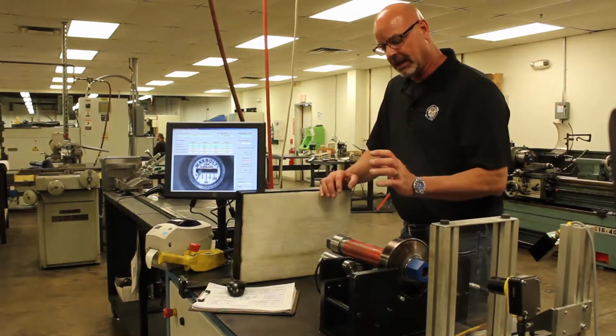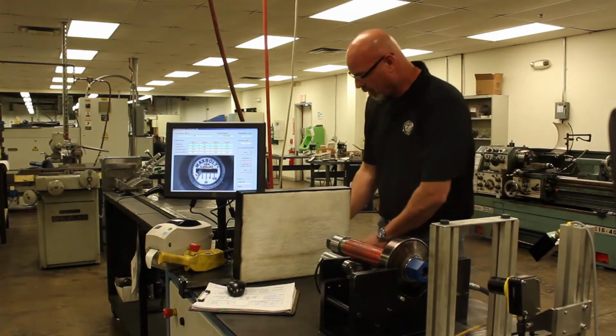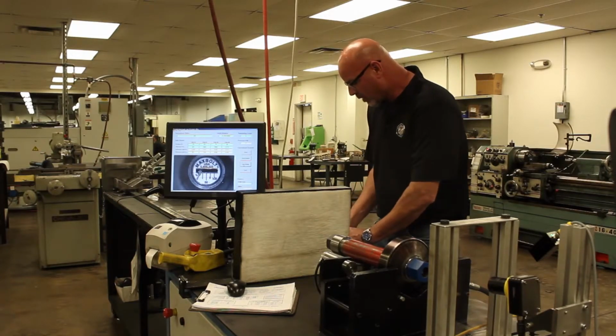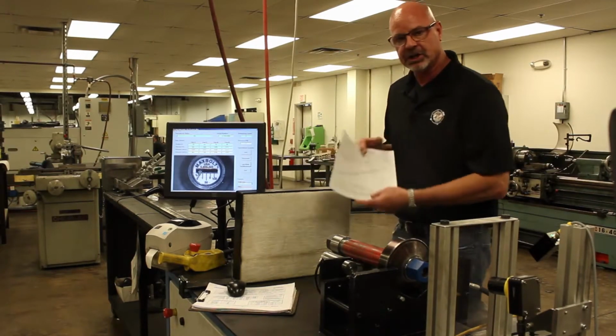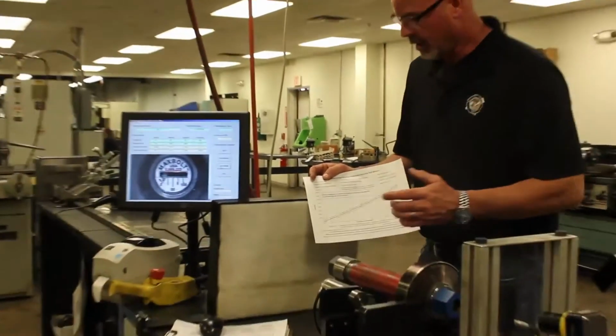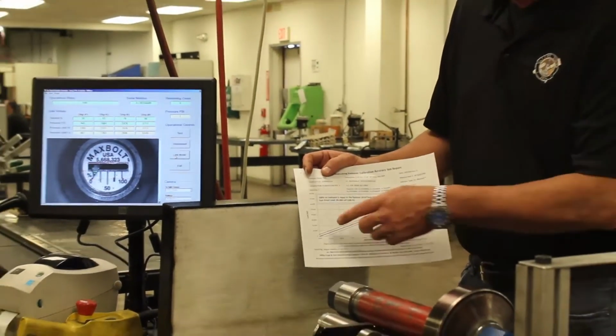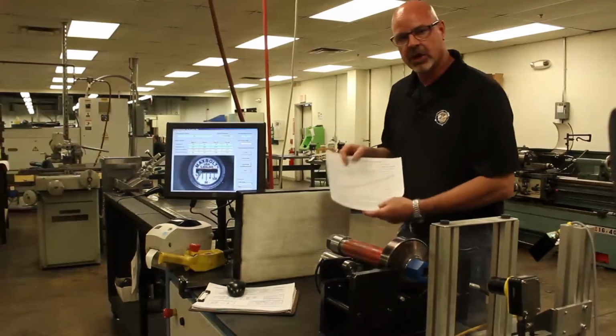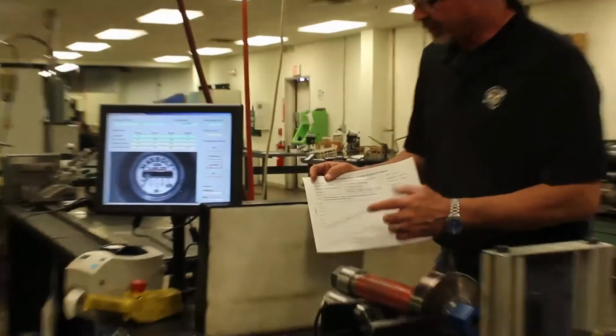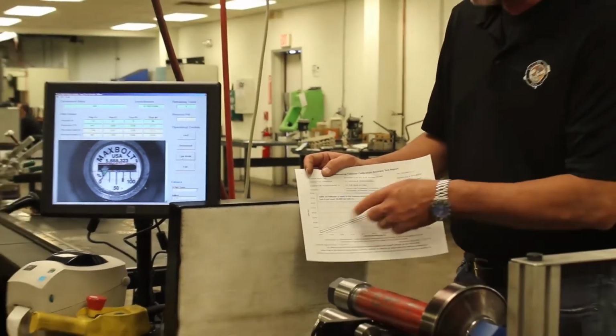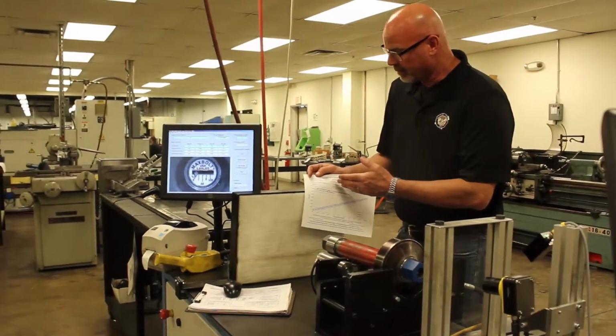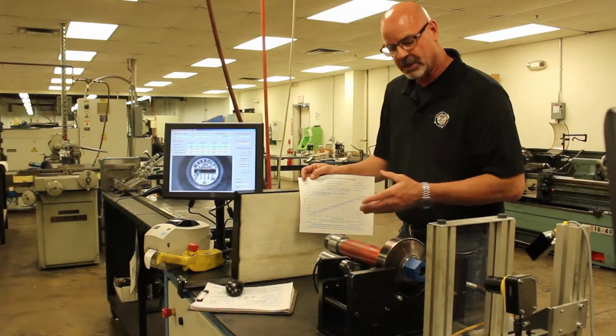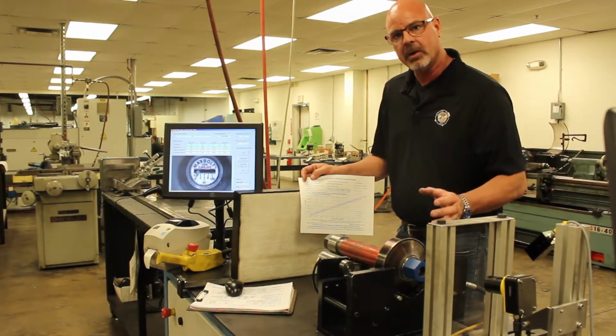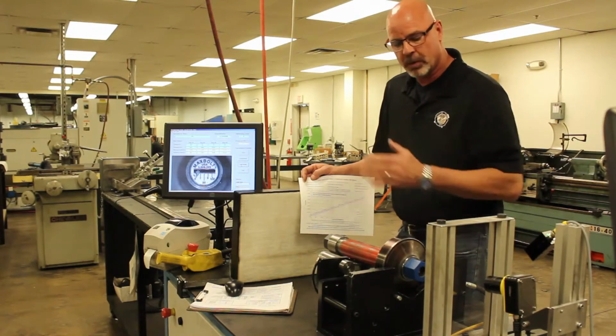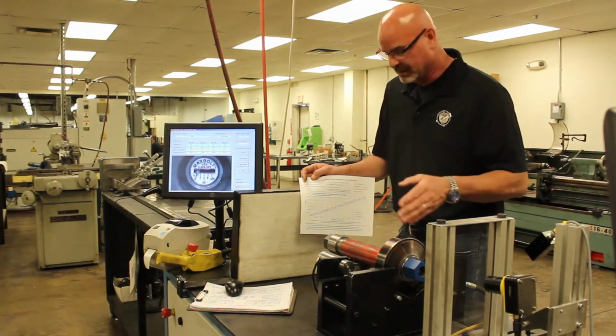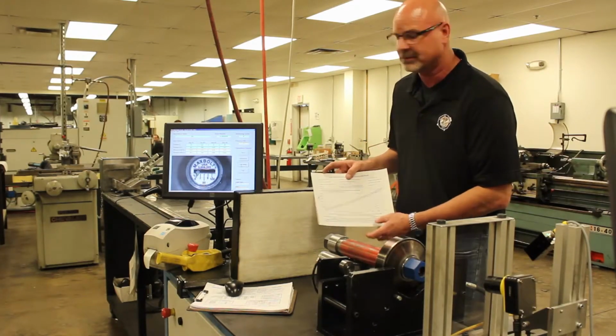calibration. The reading of the max bolt or SPC4 in the calibration process, how do you trust that number? Well, in our calibration, you get a chart that is proven out from this process that shows you the calibration of the unit at the different percentages. We plot it for you. You've got the serial number of the part, you've got the part number, you've got all the information about the actual fastener and how it was pulled. So with that, we're going to run a part test on this part in this machine, and you will see the calibration process.